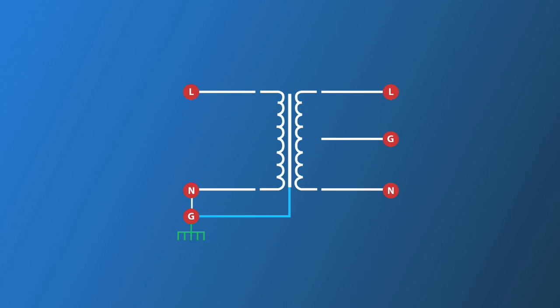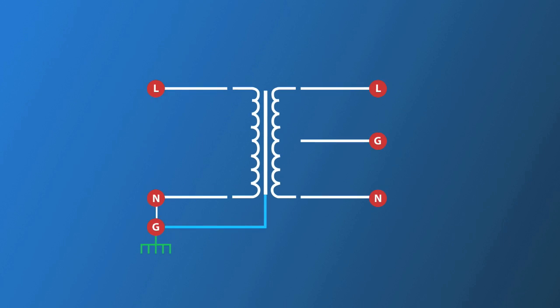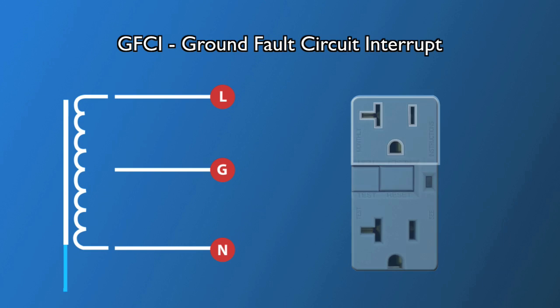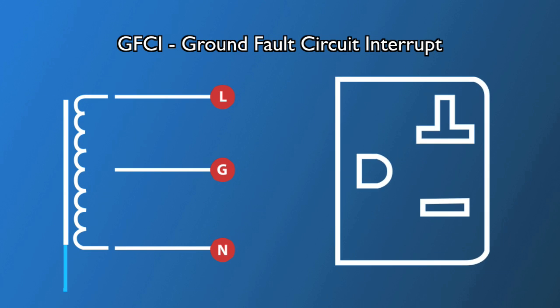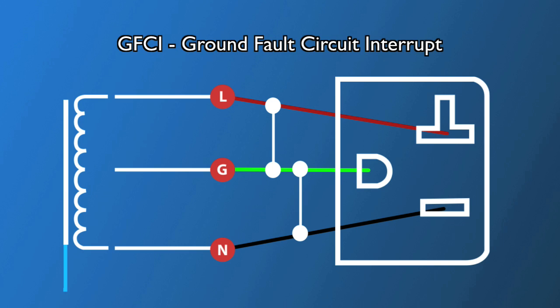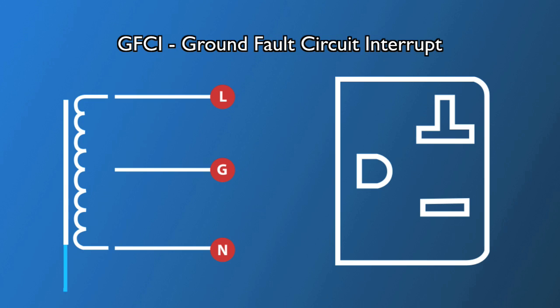To do this, it is critical that the transformer be safeguarded with a GFCI, ground fault circuit interrupt. This protection device assures that if there is any current leakage from line to ground or neutral to ground in excess of 5 milliamps, the circuit disconnects. This assures safe operation well beyond even that of a typical AC tap.